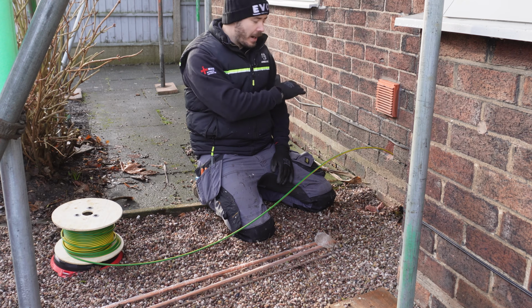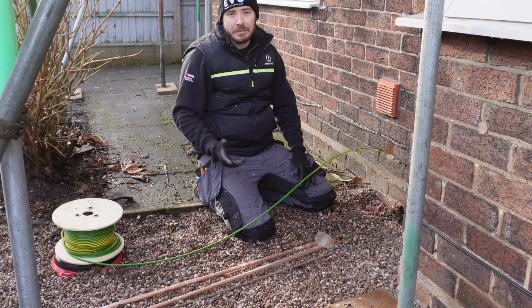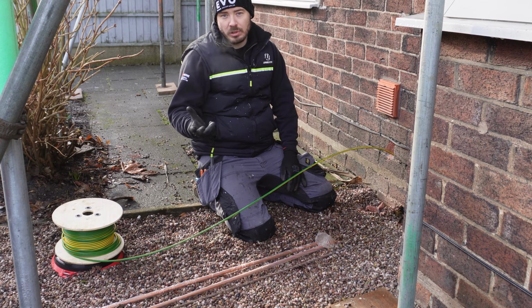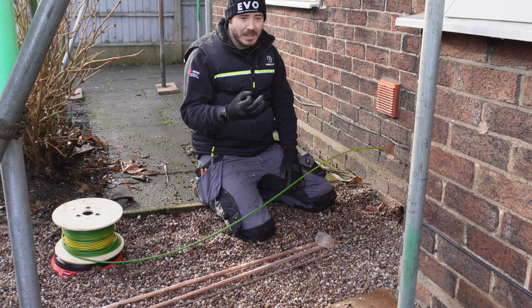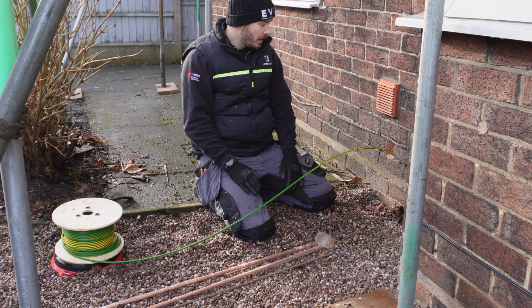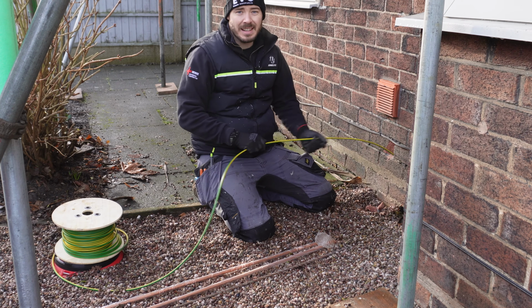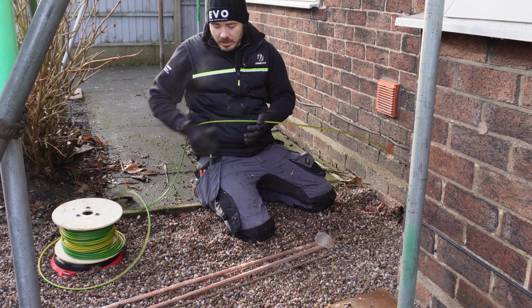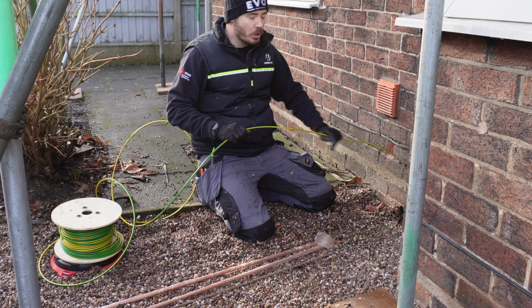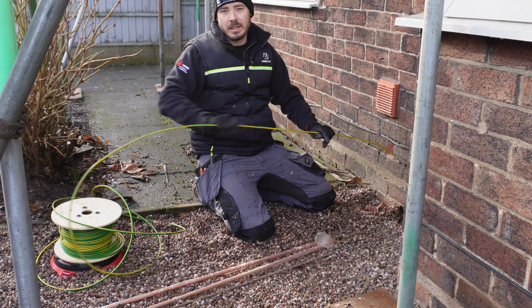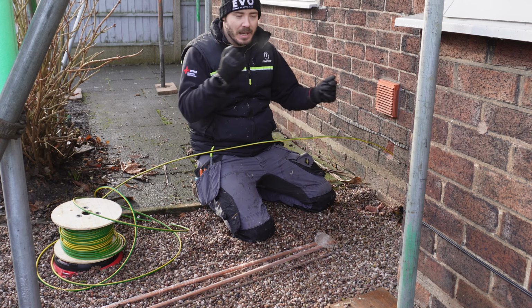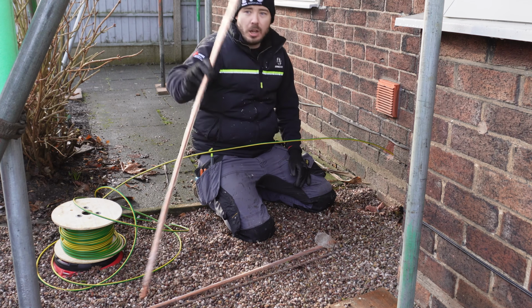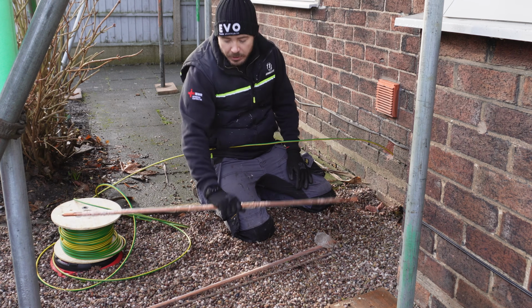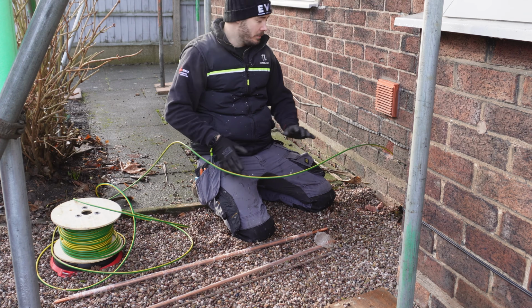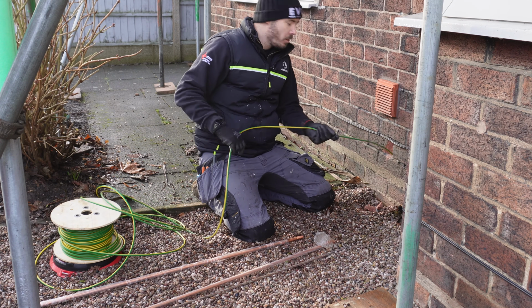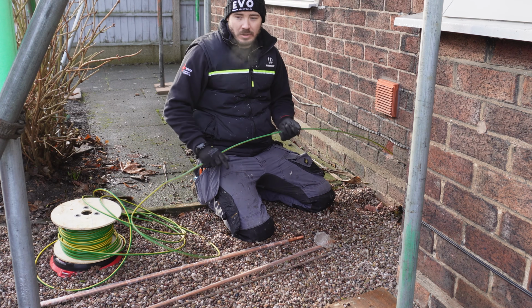We're using fireboard to mount the equipment on, that's like 58 quid a sheet. Some more EV Ultra cable, which is the Doncaster cable, high tough, with the data cable running through it - we get it in 100 meter drums, and that's 750 quid. So when we're quoting jobs and we're a little bit more expensive, it's because we're using products like that, rather than using armoured cable and then running a data cable tying it to the armoured, which looks rubbish. Earth rods, we're using the thicker earth rods rather than the thinner ones, just so we've got a better reading. I feel like everything's just done right, rather than being a sales company just to shift boxes.